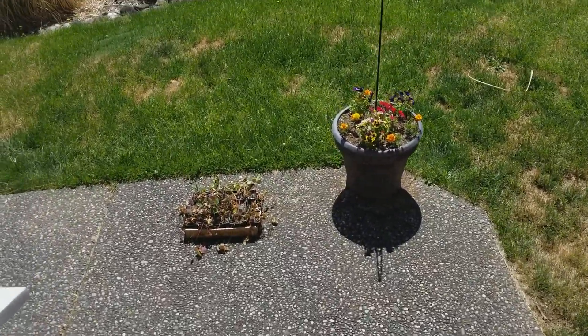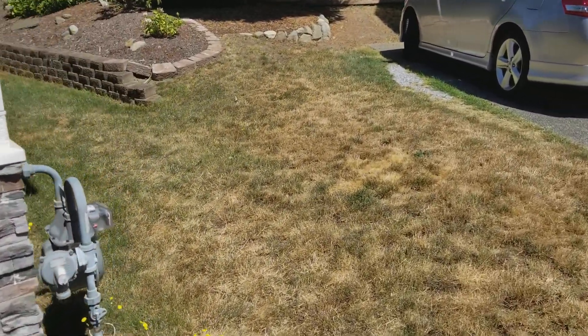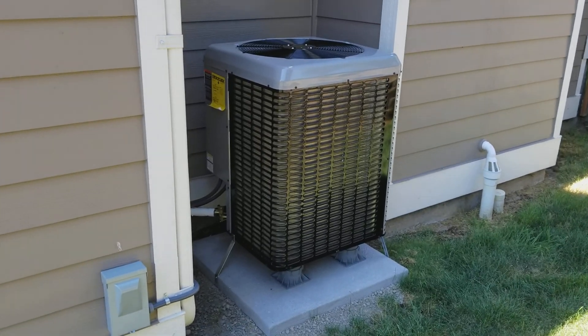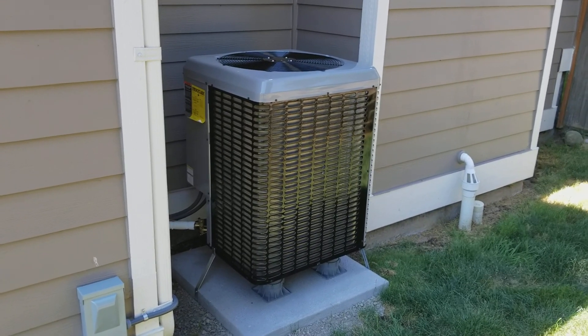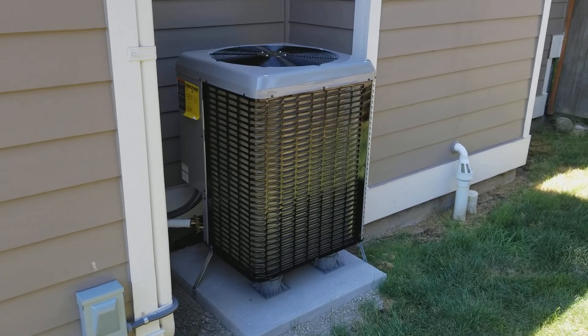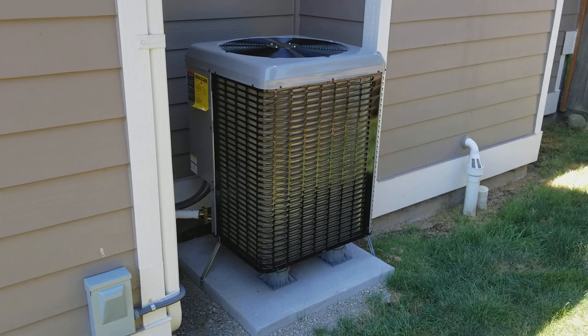The hardest part about all this is the sheer brain power — the durability of your brain while you're trying to figure this stuff out. I spent an hour here the first time they wanted AC and I knew I couldn't just dump a regular AC in this house. I ended up coming back for four hours — we dug into the house, did the blower door, did infrared, went round about on the zoning, figured out what to do about the basement, and how to balance the airflow. On a job like this, it's important that someone comes back and checks things. I changed the constant fan speed. The guys did an amazing job — everything I needed happened — but there's always a little thing here and there. I checked the fan speed of the Panasonic downstairs, that kind of stuff.